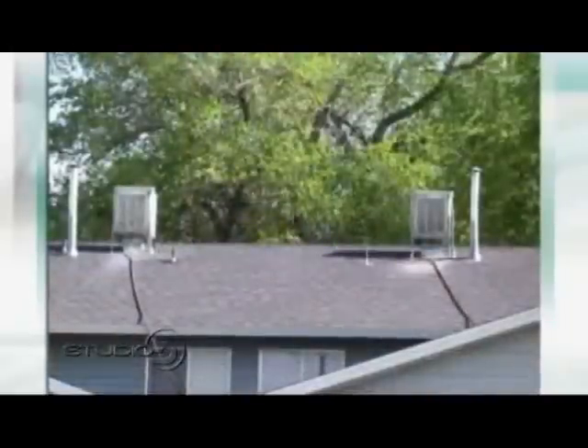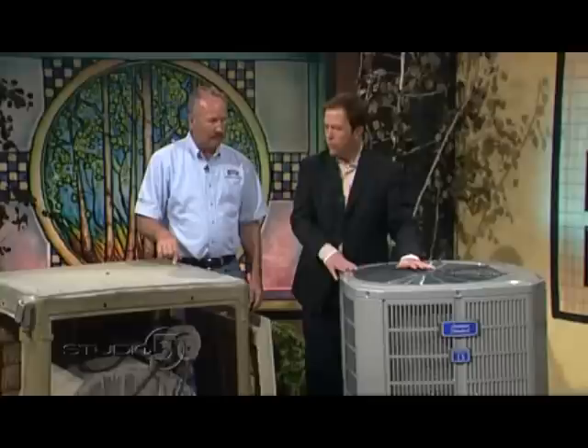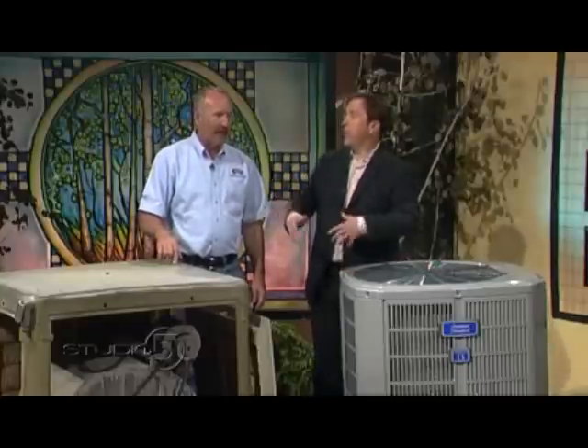People initially think they'll be better off cost-wise since it takes a little less electricity to run a swamp cooler than an AC unit. But the real problem comes in the wintertime when you have all that air going out the hole in the roof — where the swamp cooler duct comes through the ceiling. A lot of people, that is just like a chimney for heat in the winter. Unless you really seal that up well, you're gonna lose all that heat you've just paid for through your gas furnace, and it's just escaping out — and you don't even know this.